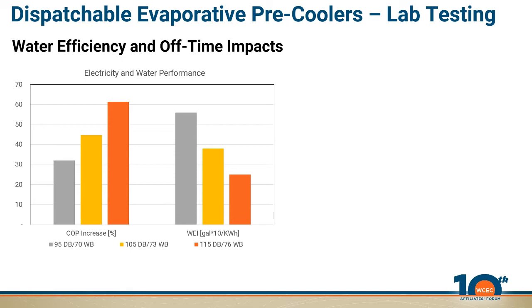In terms of water efficiency, this is a water energy index — gallons per kilowatt hour, multiplied by 10 so it fits on the same scale. As it gets hotter, going from 95 to 105 to 115 degrees, the amount of water it takes to save a kilowatt hour goes steadily down. So the more extreme the conditions, the more value you get for every bit of water used.